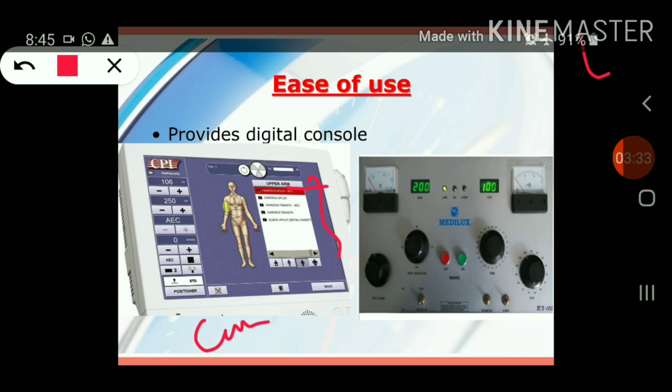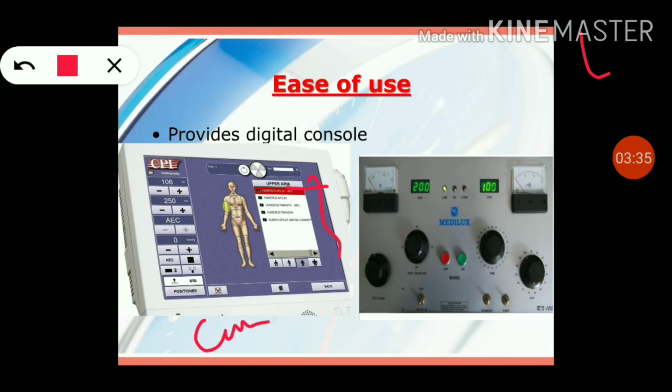In previous days, on the control panel we had to preset these knobs. Originally the operator had to set kV, mA and exposure time for each exam, and if the calculation was not proper, they could end up doing many retakes and giving a higher dose to the patient. So the high frequency generator makes the X-ray procedure much easier to use, with less calculation.